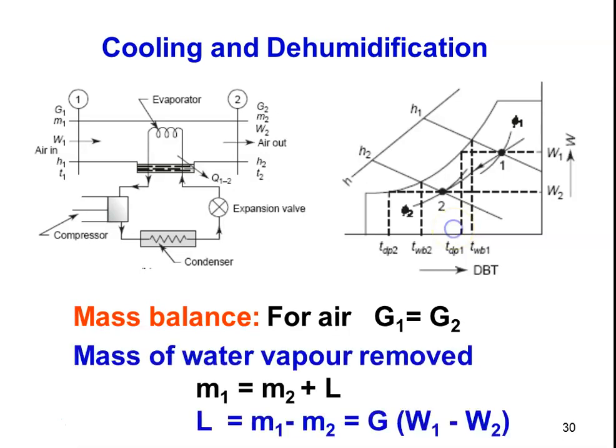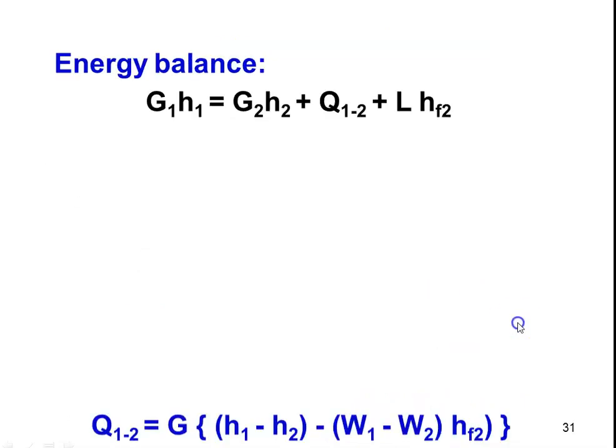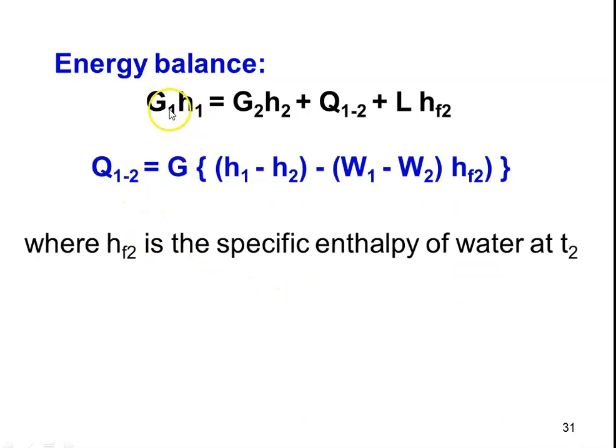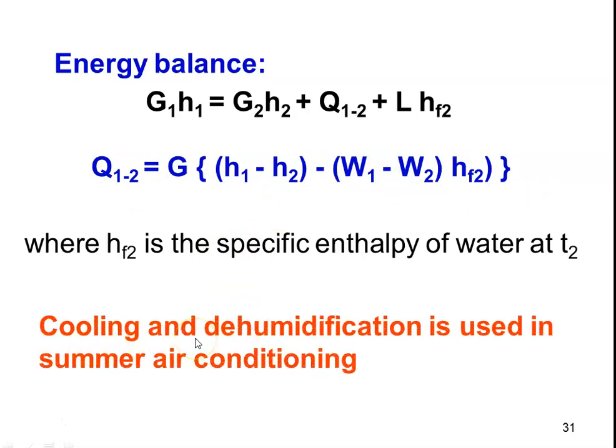For the mass balance: G1 = G2 for air; for water vapor, M1 = M2 + L, so water vapor removed L = M1 − M2 = G·(W1 − W2), which is the mass of air times the change in specific humidity. Writing the energy balance: G1·H1 = G2·H2 + Q₁₂ + L·HF2. Therefore Q₁₂ = G·{(H1 − H2) − (W1 − W2)·HF2}, giving the amount of heat removed during cooling and dehumidification.